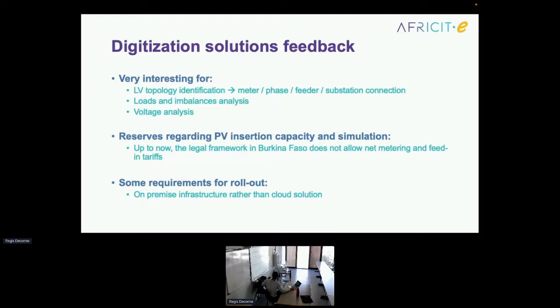For the load and imbalance analysis, mainly because it has an impact on the voltage issues, and they have a lot of under-voltage customers supplied with too low voltage. Some reserve regarding PV, as I said, no legal framework for net metering and feed-in tariff for the moment. And a requirement for rollout that we see often is that everything needs to be on-premise infrastructure, no cloud solution - they don't really appreciate cloud solutions.